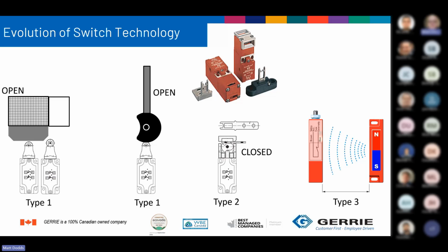Type 2 is in the normal or rest position when the actuator is present, or when the guard is closed. The actuator is physically attached to the door and must be removed from the switch to actuate the contacts. This is similar to type 1 with the movement of a cam to actuate the contacts. So let's show the animation there where, again, as I pull the key out, it rotates the cam, forces down a set of contacts, and opens up the circuit.